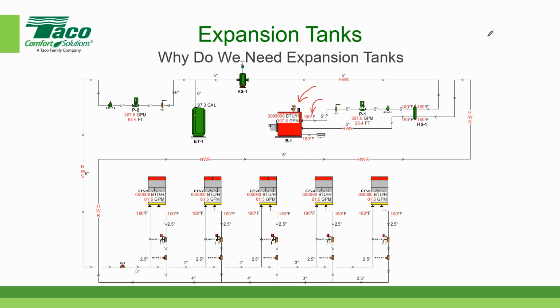When fluid expands, it has to have some place to go, so it goes inside the expansion tank. I'm going to talk a lot about expansion tanks this evening. So why do we need them? We have a closed loop pressurized system, and when we add heat, the fluid - in this case water - expands as a function of being heated up. It needs a place to go, and that's what the expansion tank provides, allowing the fluid to expand without any negative effects on the system. Every closed loop system will expand with an increase in temperature, and that fluid has to have some place to go.